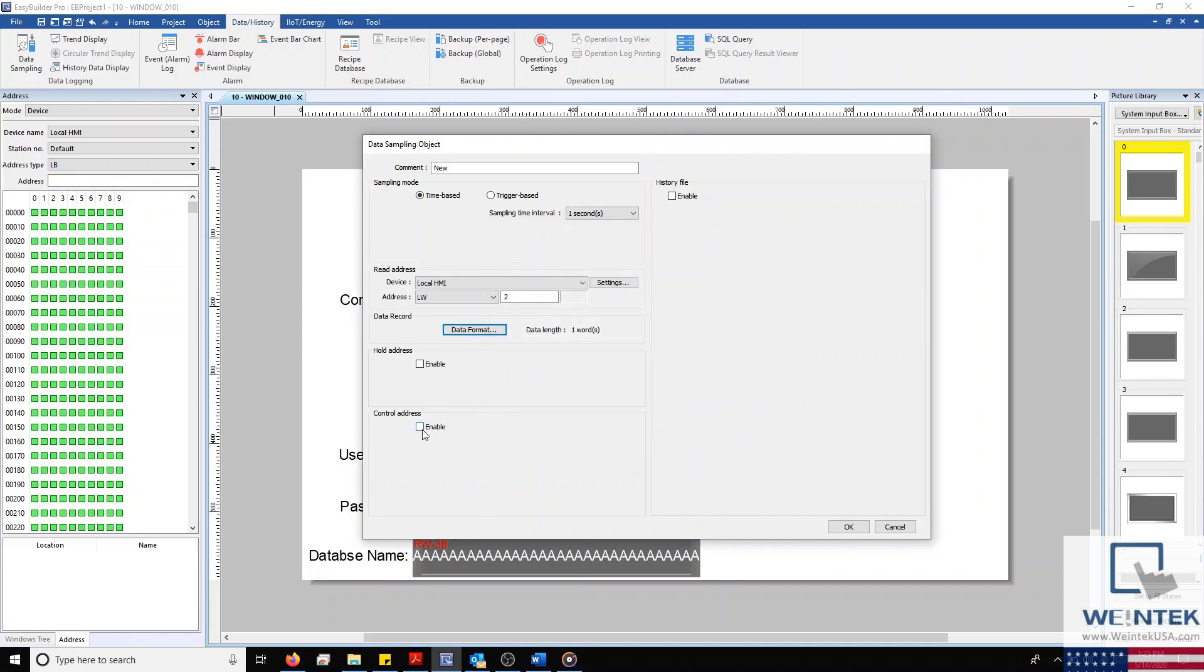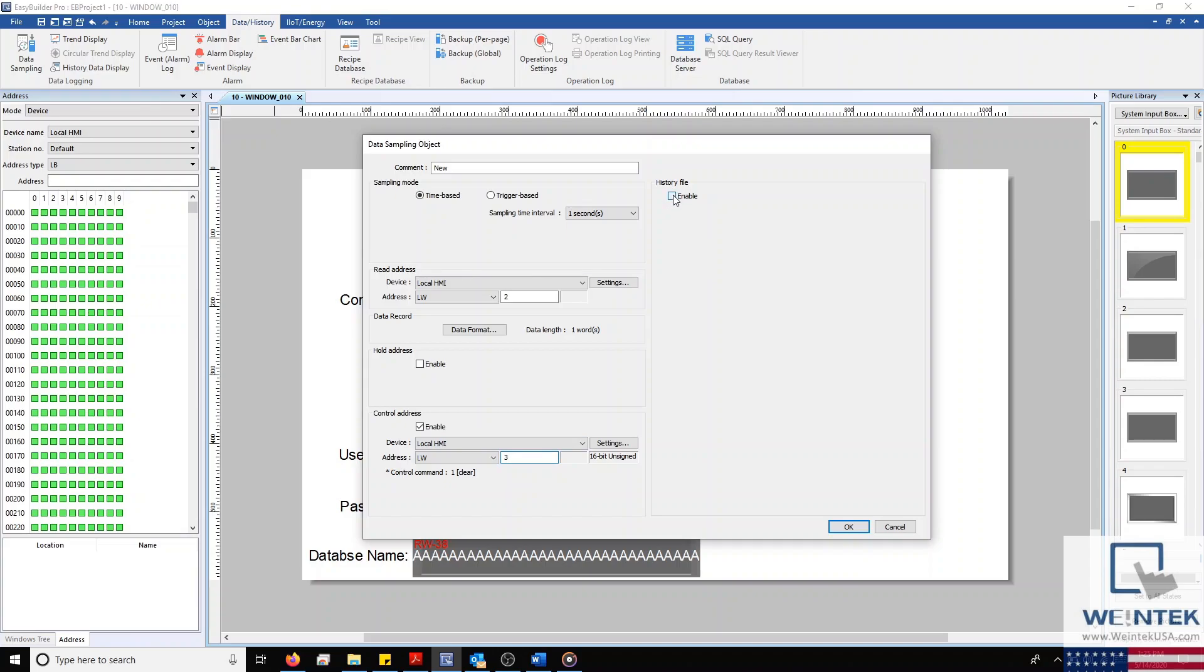I'll then enable my control address and set it to our HMI's LW3 internal register and then enable history files as well. I'm going to name this data file HMI data, and then enable sync to database and auto sync periodically.